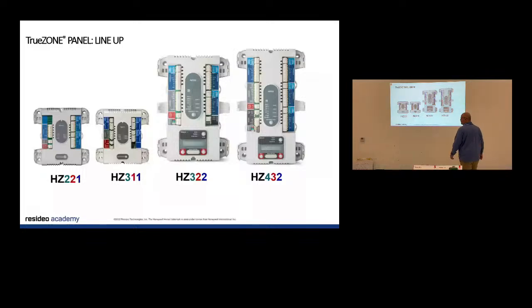But with heat pumps and dual fuel starting to take off, we only make 1 dual fuel product. It's in the selection guide. I don't care if it's a 2-zone all the way to 4-zone, you need to use this if you're doing dual fuel. So the 432 is the only one you can do dual fuel. And again, if it's less than this many zones, you're cool. If it's more than that, we gotta talk. Does everyone know what dual fuel is? Can you talk briefly about that? Absolutely.